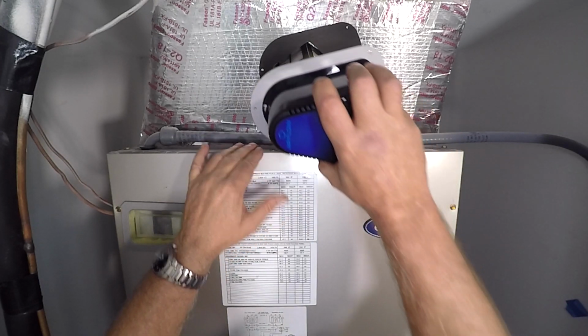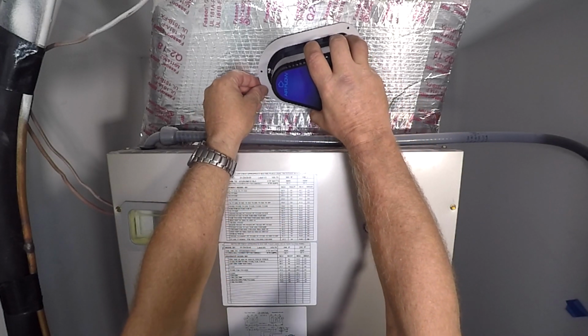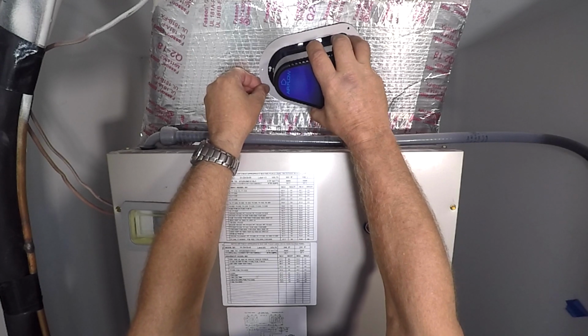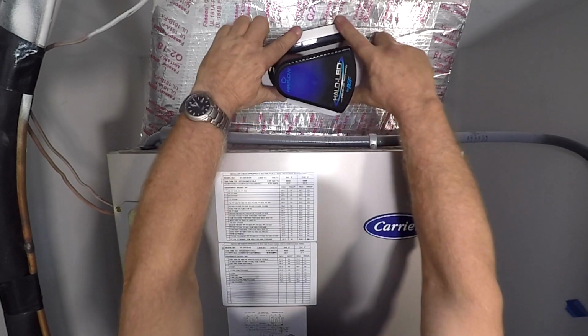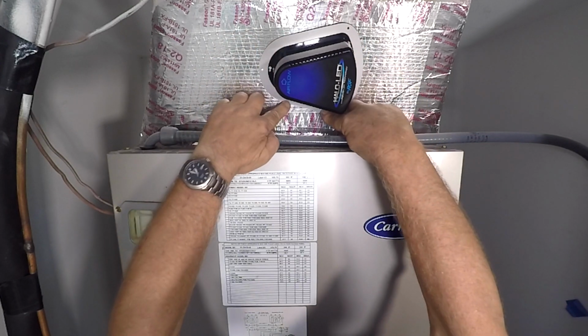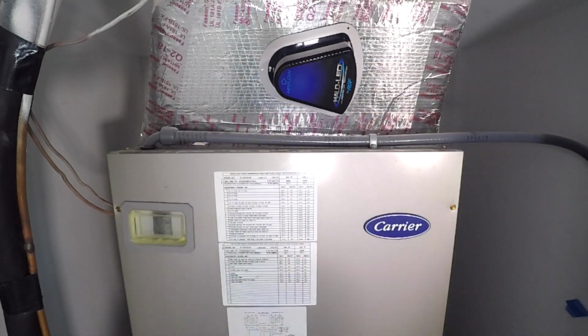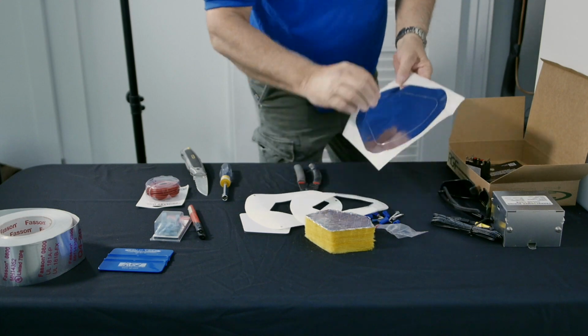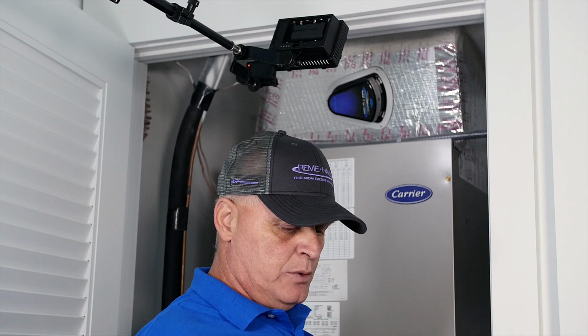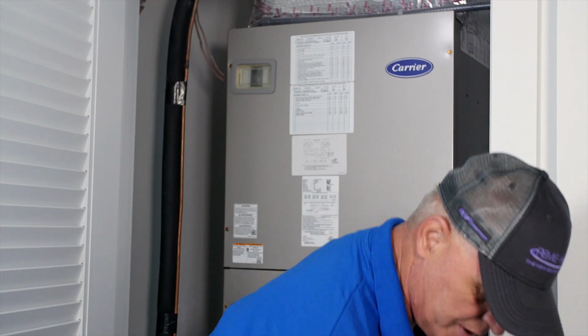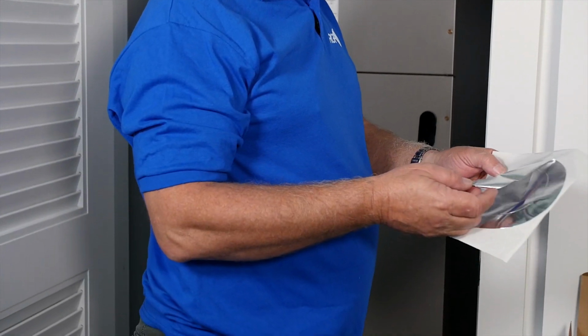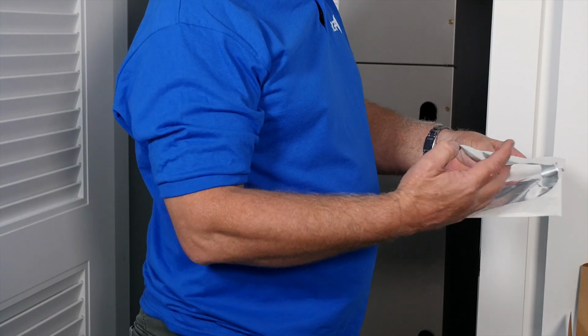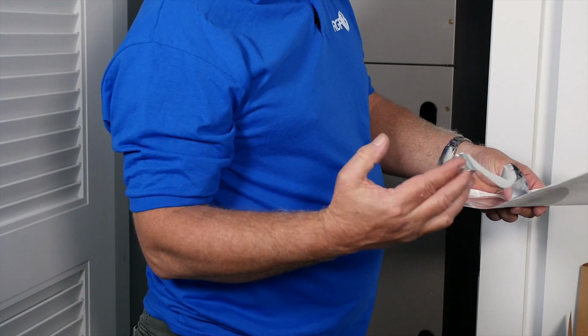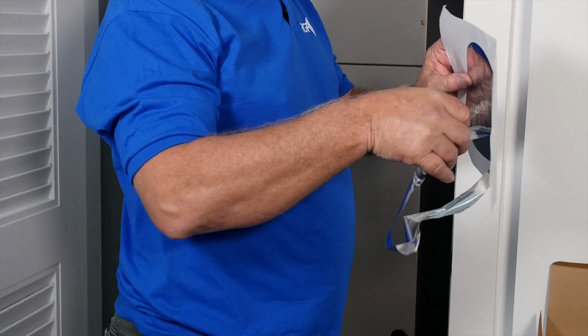It comes with an aluminum tape gasket, which we are going to attach around the unit to keep it in space and sealed. The aluminum gasket that we use with it, you're not going to be using the center of this, just the outside edge of it. This is basically your final seal of the unit.